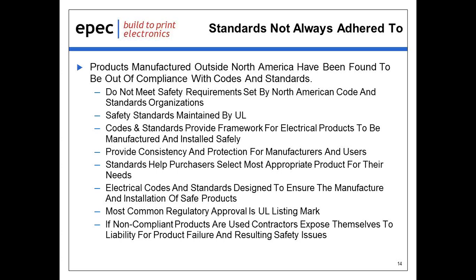When a follow-on test was conducted, which UL sometimes does spontaneously in our factory, it was found that the assembly had been made with a cable that did not meet the flammability requirements of the style printed on the jacket. Based on that, increased testing was conducted, and it was found that there had been many instances, not only with ourselves but with other companies as well, where the wrong compounds had been used in the components of the assembly, and those compounds didn't come close to meeting the flammability tests required by UL.